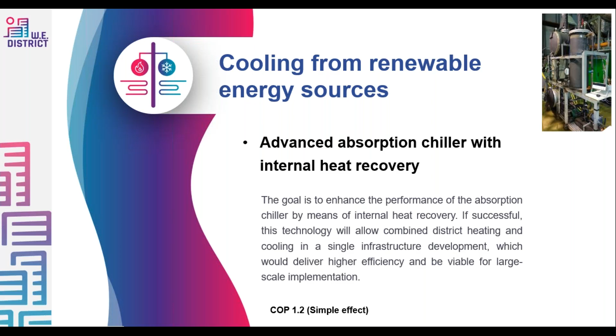The second cooling technology is an enhanced absorption chiller with increased COP, coefficient of performance, obtained by adding a step of internal heat recovery. Currently, the COP for a simple effect absorption chiller is around 0.7; in our case we could achieve 1.2, almost double, for a simple effect that requires lower temperature.